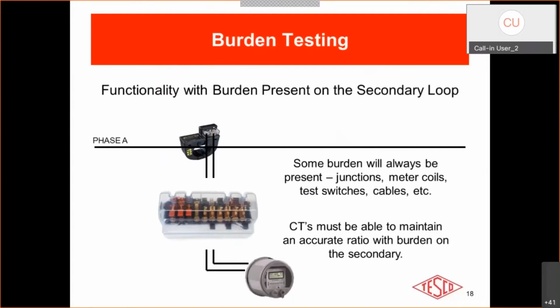Now, burden testing is a little more complex. There will always be some burden in the secondary loop of the CT. The wires themselves will inject some burden on the secondary, the test switch, the coils in the meter, and all your interconnects, wherever you connect the wiring. There will always be some burden, but it should be very minimal and negligible.